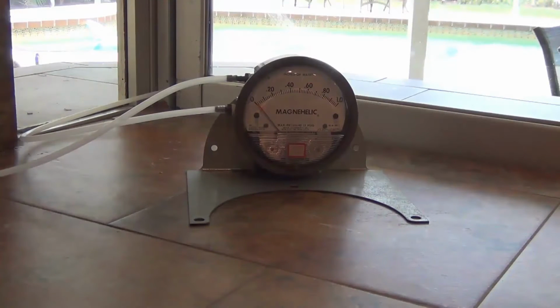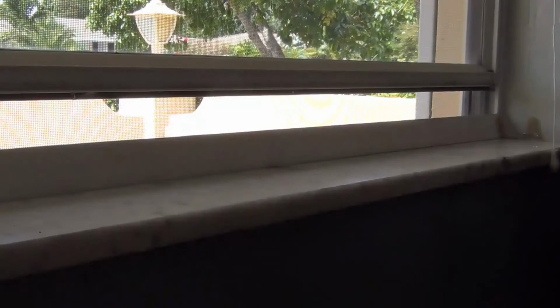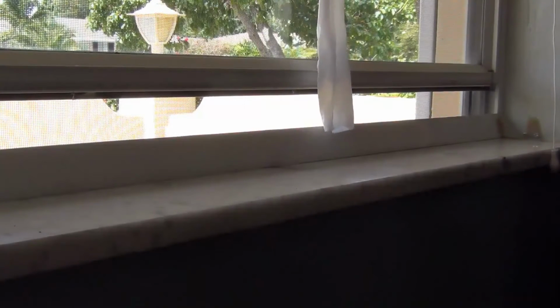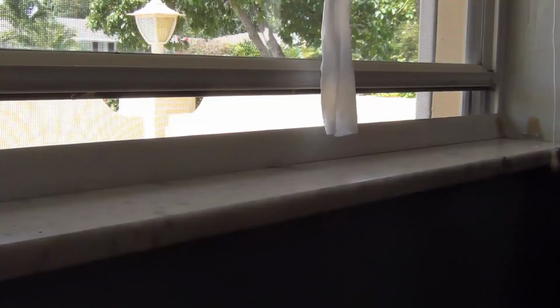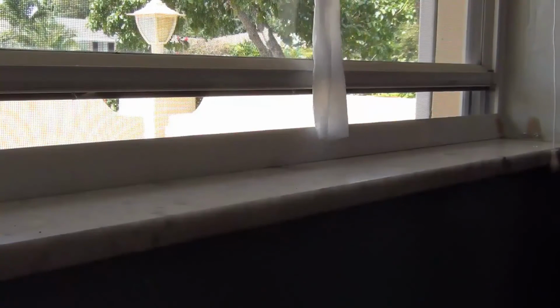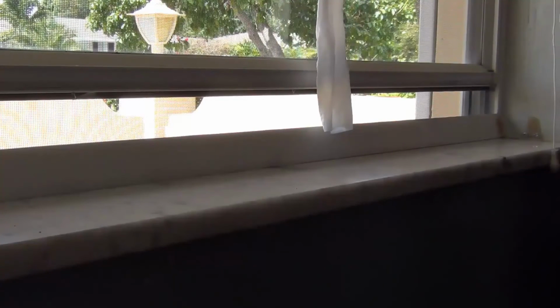If a pressure differential gauge is not available, slightly open a window in the center of the home and check if the air is moving in or out. If the air is moving out, slow down the makeup air fan using the high trim pot. If the air is moving in, speed up the makeup air fan using the high speed trim pot. Repeat this procedure for low speed operation. As previously mentioned, repeat this as necessary until the system automatically operates as desired at all speeds.